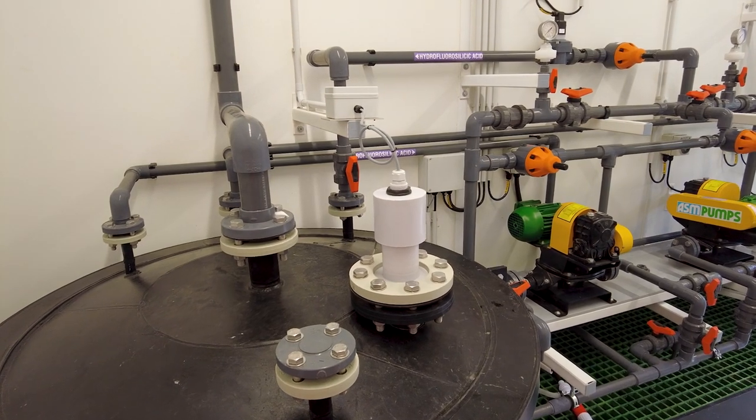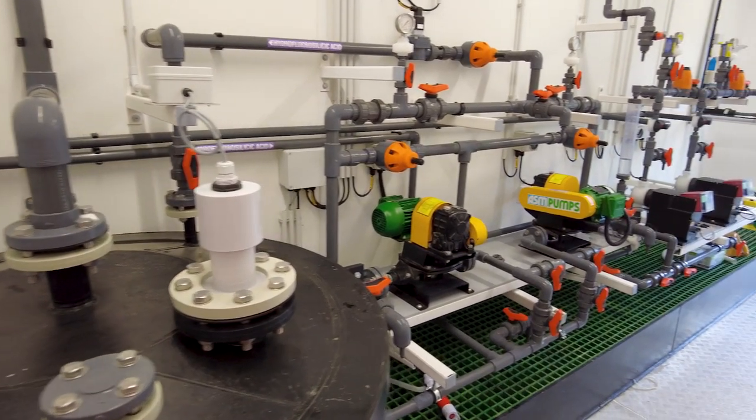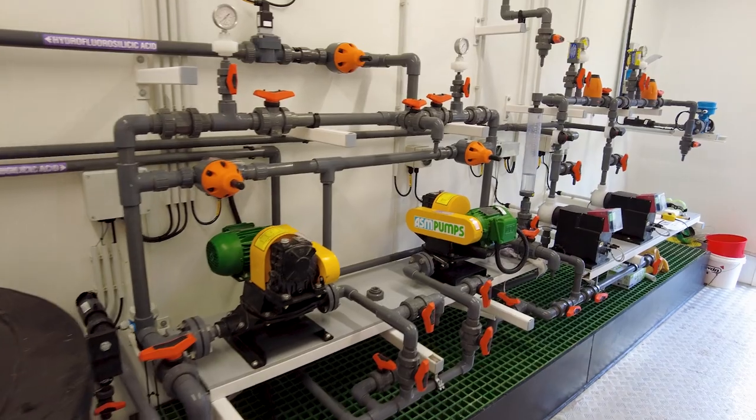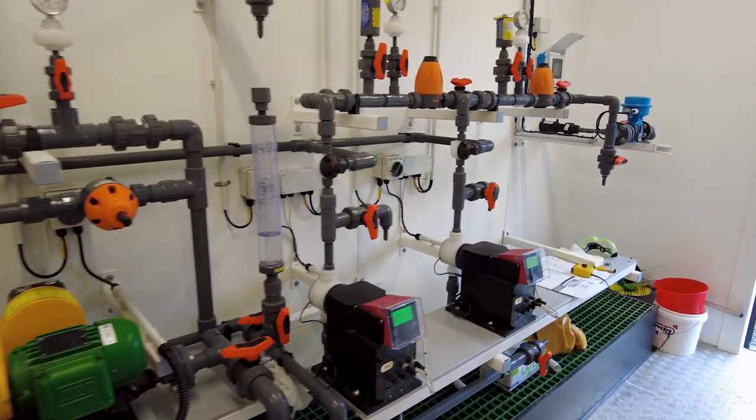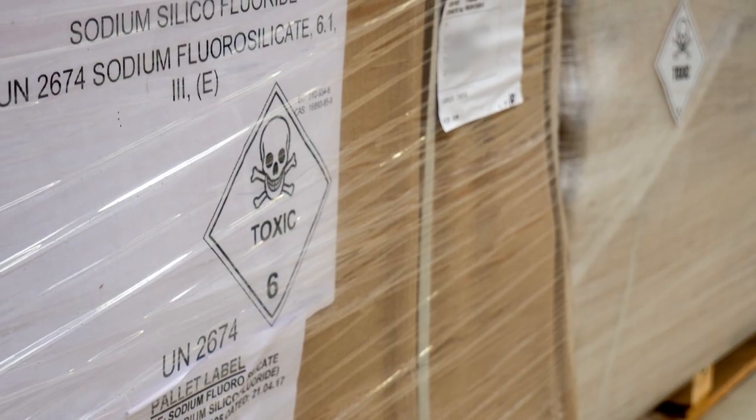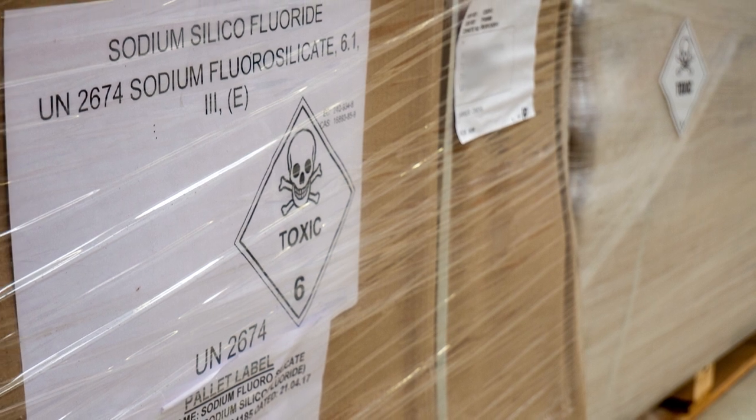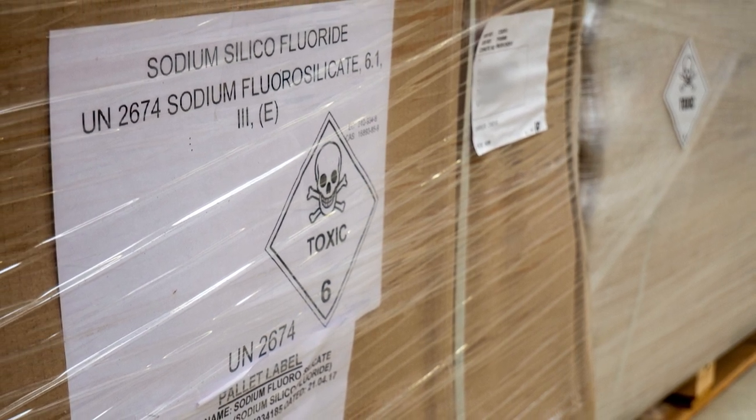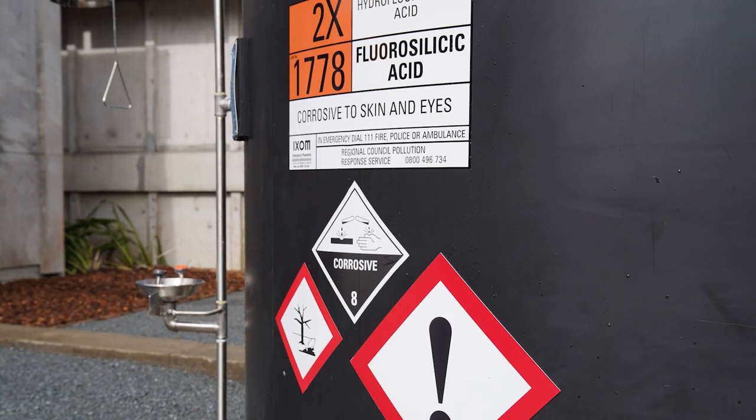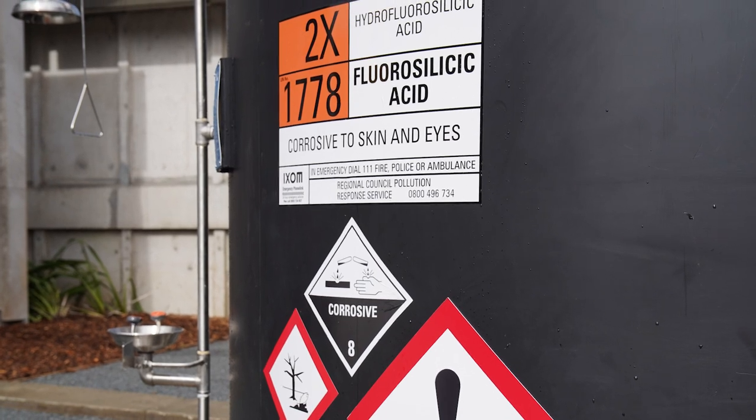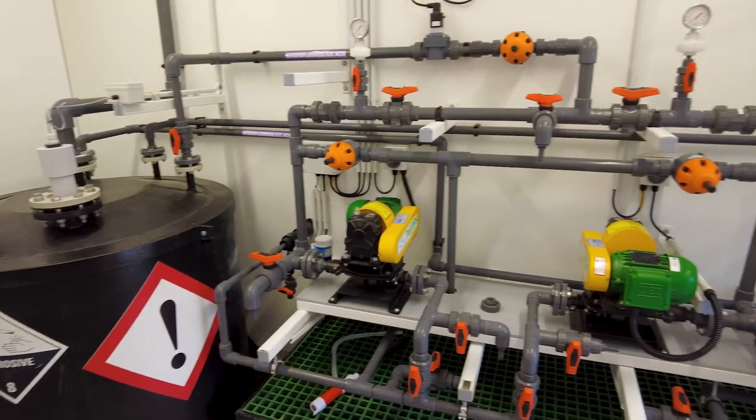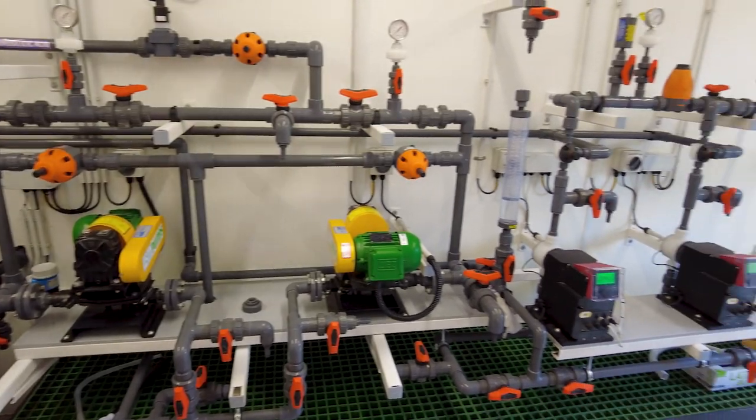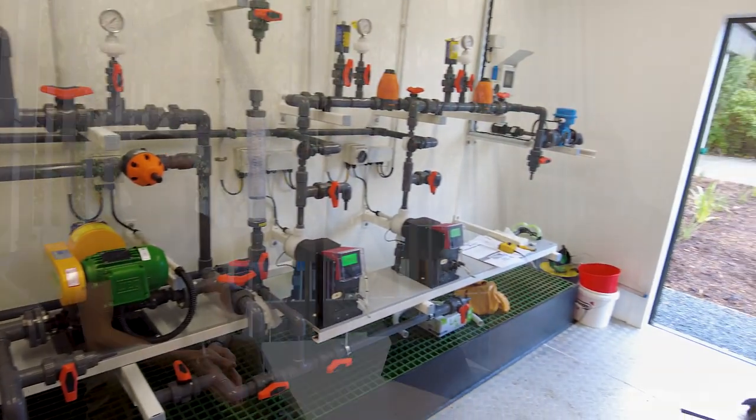Are there any dangers associated with using fluoride in water treatment? Yeah, so when it's properly controlled and dosed to the system, no. Fluoride is relatively safe. As a chemical it has its own dangers like many of the chemicals that are used for many different reasons, not just in water treatment. The powder form of sodium fluoride and sodium silica fluoride is relatively dangerous, especially if inhaled or got on the skin, but when it's diluted down and put into water it's totally fine, and in some places in the world the concentrations of fluoride in the natural water can be higher than what's used in drinking water. The liquid form, hydrofluorosilicic acid, is obviously a liquid so more prone to potentially leaking out and getting in places, but in a properly designed system again it's relatively safe if you take the correct precautions.